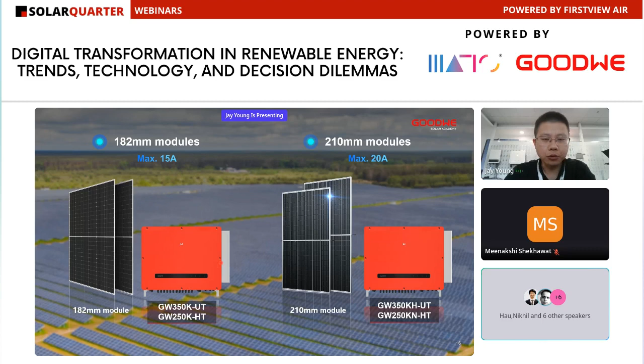So we have two solutions for the PID effects. At night, we will give the PID recovery solution. We will generate 800 volts between the PV negative and the earth to do the repair work of the PID effect. And during the daylight, we will give a similar function. We will generate a small positive voltage between the PV negative and the ground, around 7 or 8 volts. It's to prevent the modules from getting the PID effect. So for this PID effect, we have a 24-hour solution for the modules.